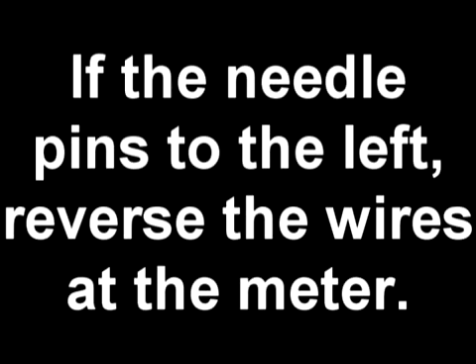And if the needle seems to go to the left, it pins off to the left side of the meter, that means you've got the leads reversed. Positive is negative, where negative should be positive. Pull the wires from the meter, reverse them, the black to red, the red to black, and then try again.